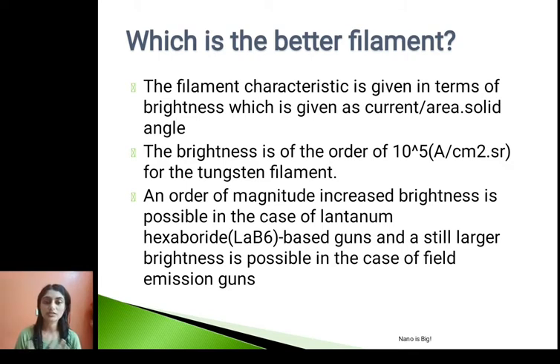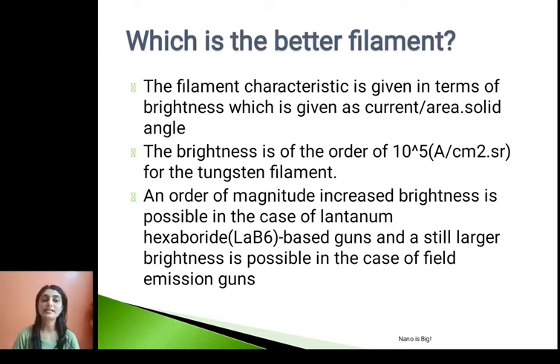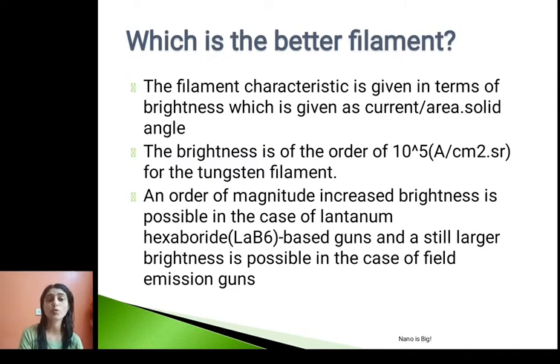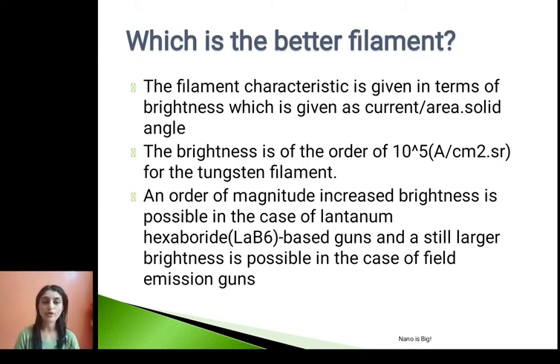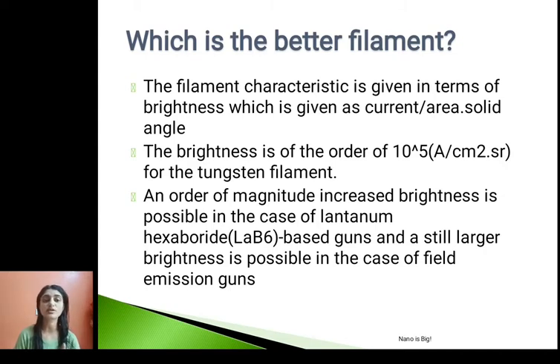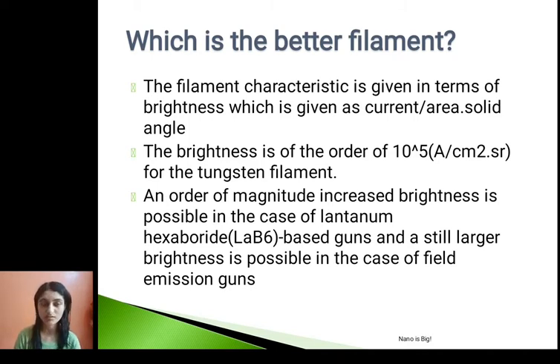The filament characteristic we measure in terms of its brightness, and this brightness is measured in units of current per area per solid angle. The brightness is of the order of 10⁵ ampere per centimeter squared per steradian — this is for the tungsten filament. An order of magnitude increased brightness is possible in the case of lanthanum hexaboride (LaB6) based guns, and a still larger brightness is possible in the case of field emission guns.